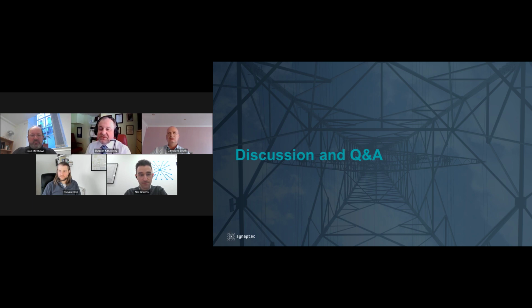Yeah, let me maybe try. There are some experimental deployments at some utilities on the west coast of the US where they have some actual data. When you look at the down conductor, just because of how gravity works, you will have more than a second before that conductor hits the ground. So any method that is able to detect an open phase condition will have enough time to clear that, to de-energize that feeder. So when the conductor falls down, there is no real energy pumped into that spot.